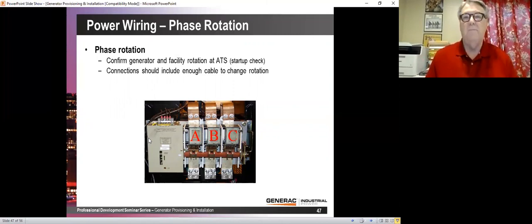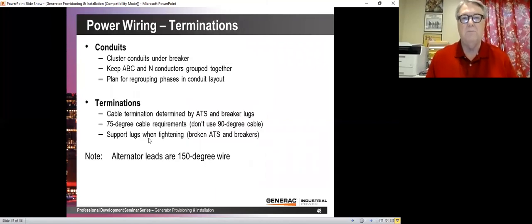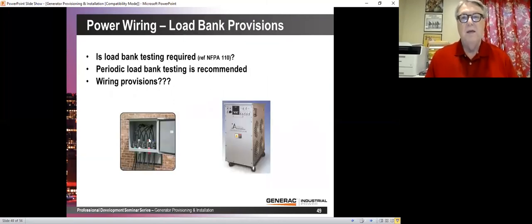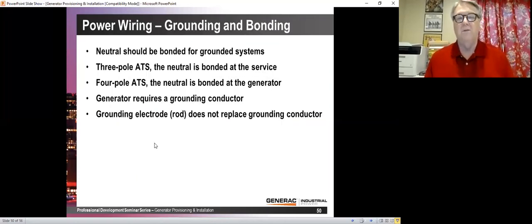Phase rotation obviously is very important, but electricians generally are very good at making sure that the phase rotation of the generator is appropriate. We have conduits. Again, the terminations are generally 75 degrees. This is just standard wiring practice. Load banks are getting more popular. This is a place where we actually put a connection point outside for the load bank, makes it really nice. And you should load bank a diesel generator at least every couple of years to make sure you don't get wet stacking.